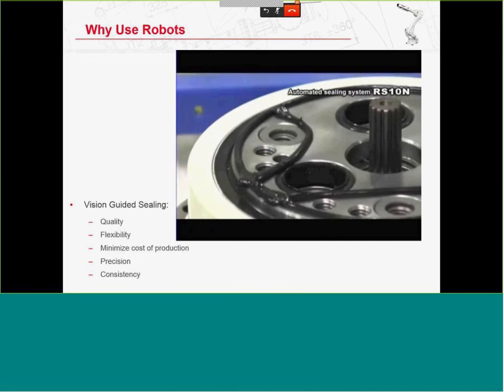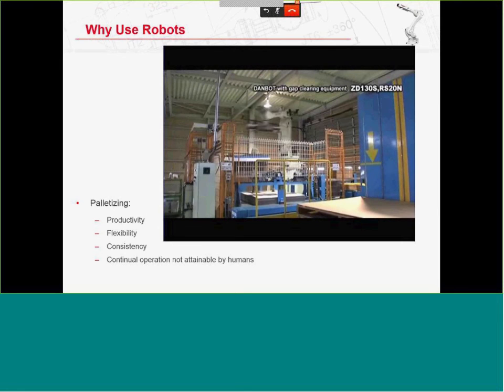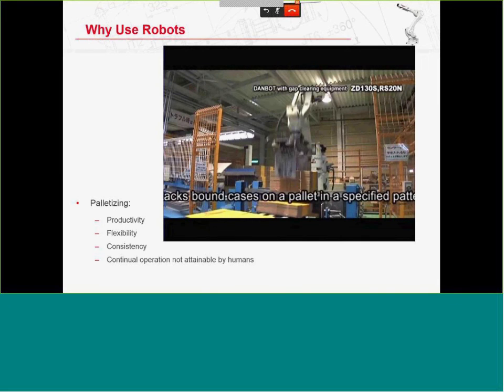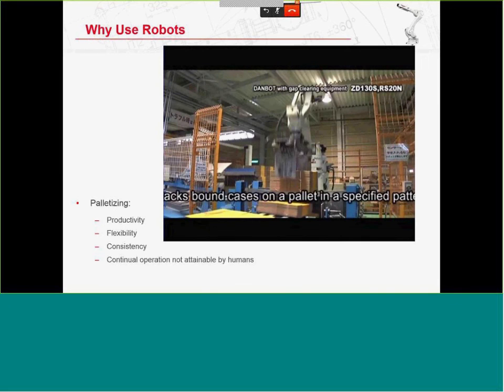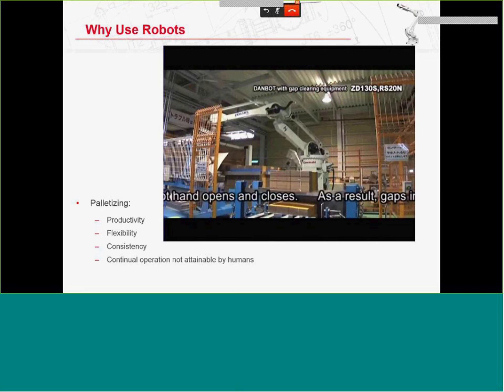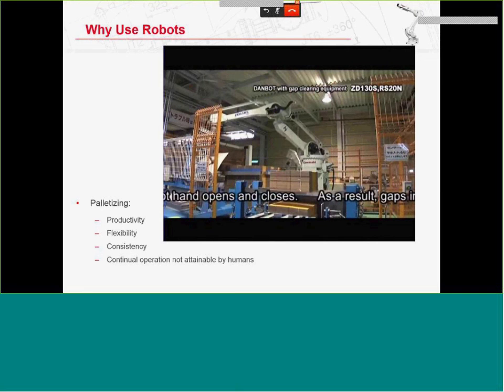Here's an application of a four-axis palletizing robot with 130-kilogram capacity. It has a special adjustable servo-driven gripper, picks up cardboard packs from an infeed conveyor, and builds a stack. This robot can cycle as fast as about 28 times a minute. The adjustable gripper gives flexibility and consistency — it also places slip sheets to separate different layers.